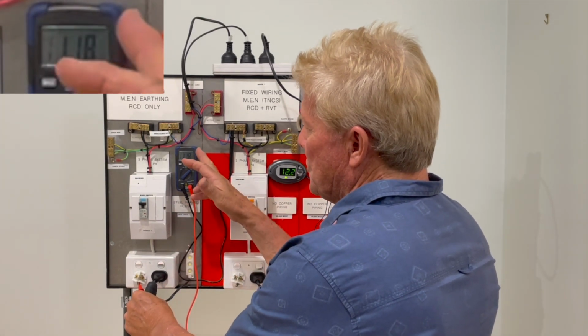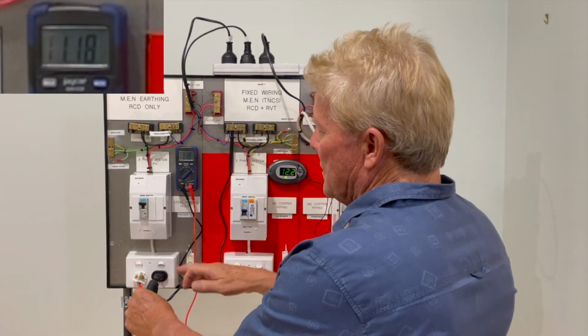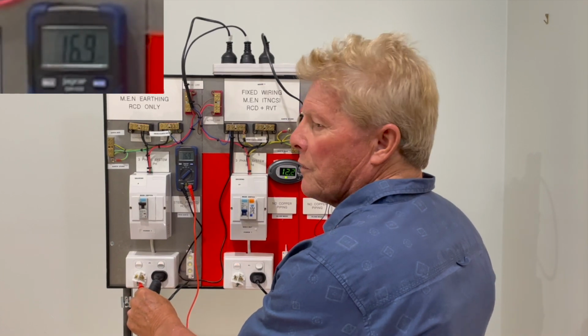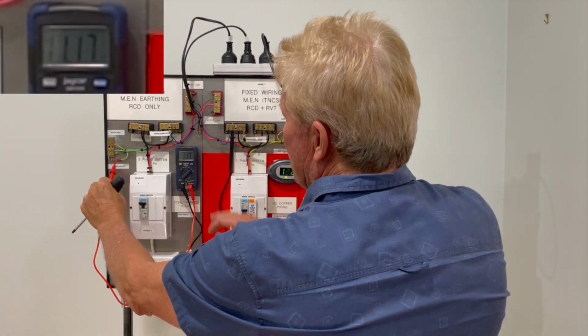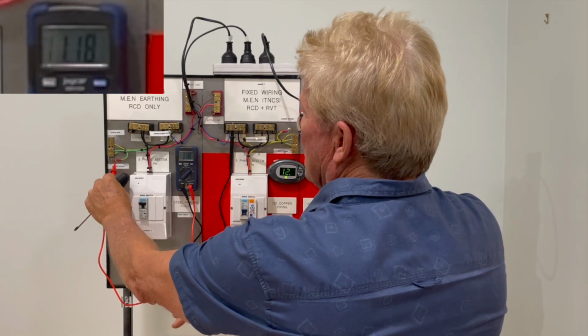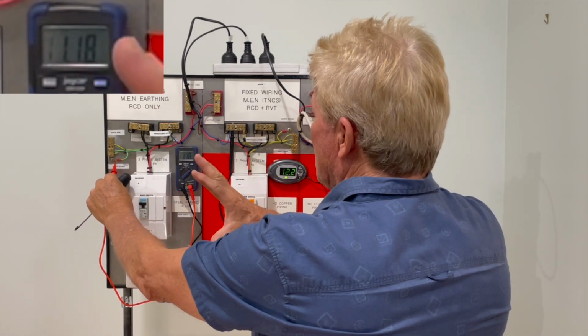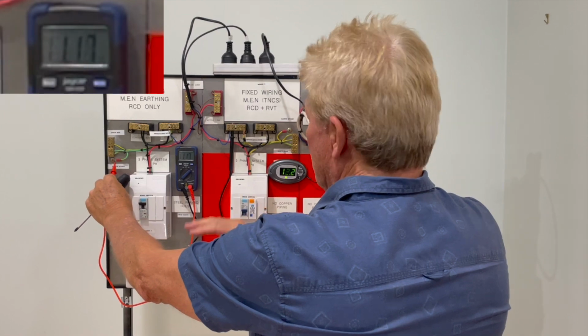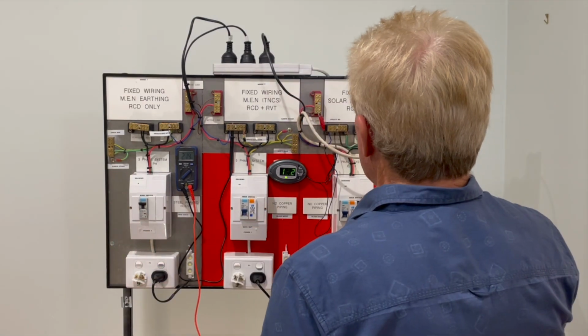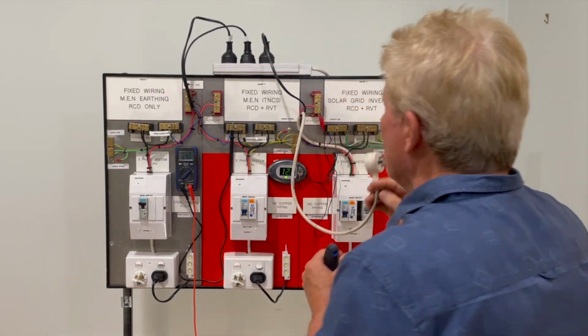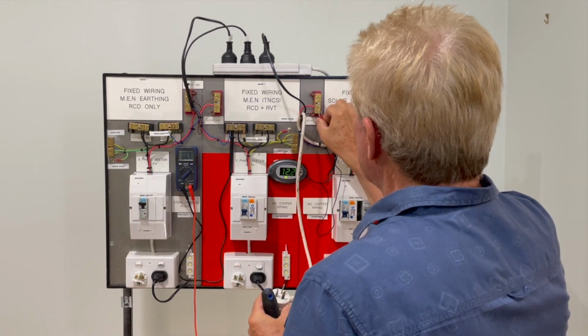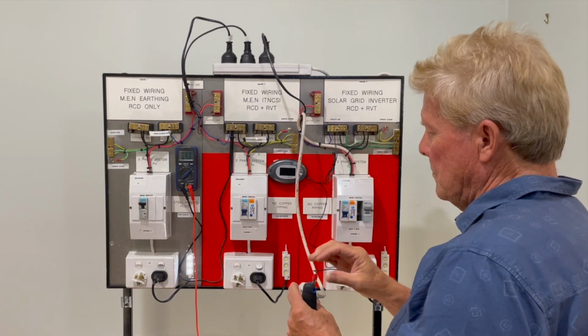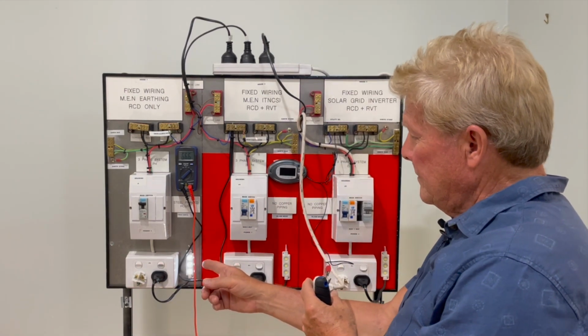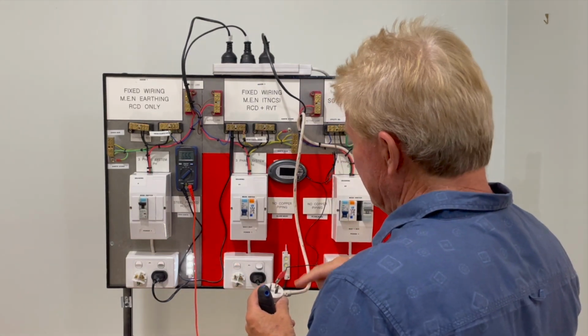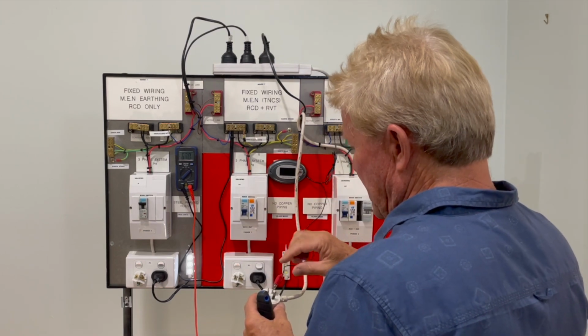But you've lost your neutral. These houses have lost their earth, and yet on this earth, you've got nearly 12 volts on the earth. So if we go to now, we've got 11.8. That's in the ground, that's in house 1. So that's on all your gas, any external piping, any of your EV charging or anything like that. So if we take this one off here, this is our solar on house 3. If we take that off there, look what happens. We get our load because we've reconnected this through the solar. That's how much power is going through this unit here.